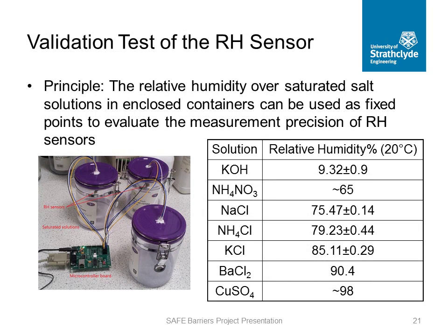The encapsulated and non-encapsulated sensors have been tested in various testing environments. The first validation test of the relative humidity sensor is proceeded in enclosed containers above saturated salt solutions. The relative humidity above saturated solutions is considered as a constant relative humidity reference point, thus can be used to evaluate the measurement accuracy of the relative humidity sensors. The chemical solutions and their corresponding relative humidity levels are listed in the table on the right. The photo on the left shows the experimental setup of the sensors installed above the saturated solution and connected to the controller board outside the container.